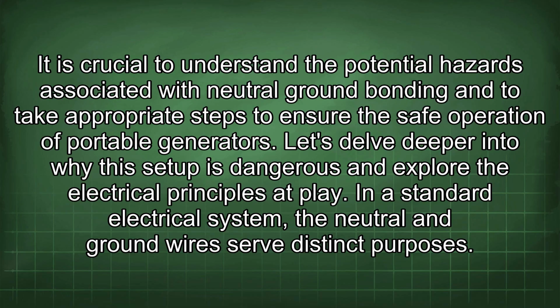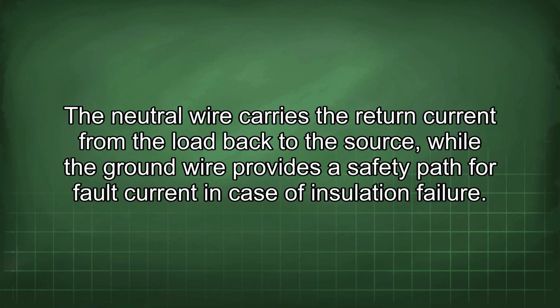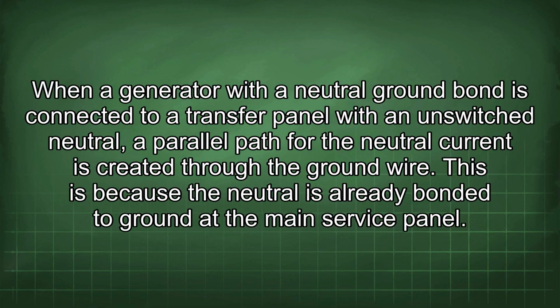Let's delve deeper into why this setup is dangerous and explore the electrical principles at play. In a standard electrical system, the neutral and ground wires serve distinct purposes. The neutral wire carries the return current from the load back to the source, while the ground wire provides a safety path for fault current in case of insulation failure. When a generator with a neutral ground bond is connected to a transfer panel with an unswitched neutral, a parallel path for the neutral current is created through the ground wire. This is because the neutral is already bonded to ground at the main service panel.